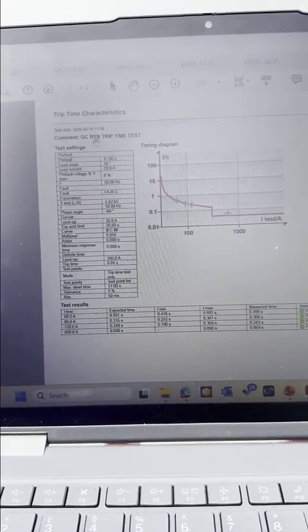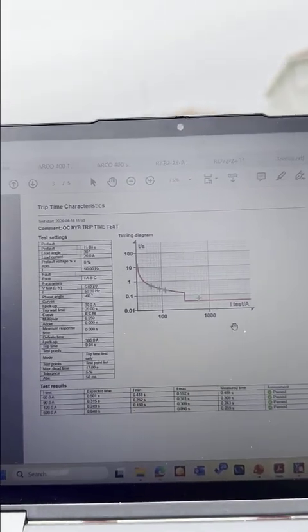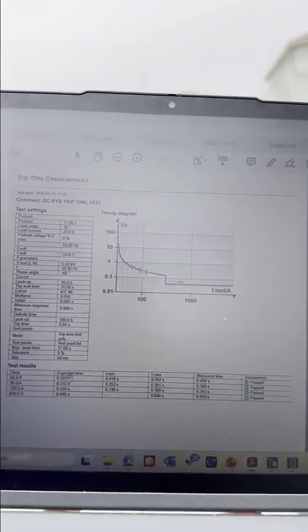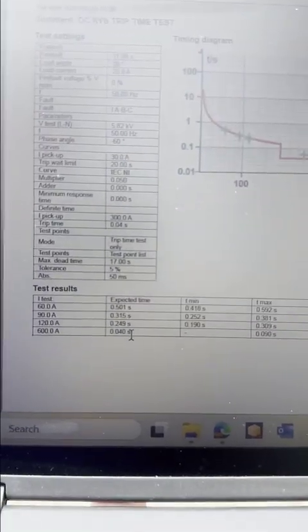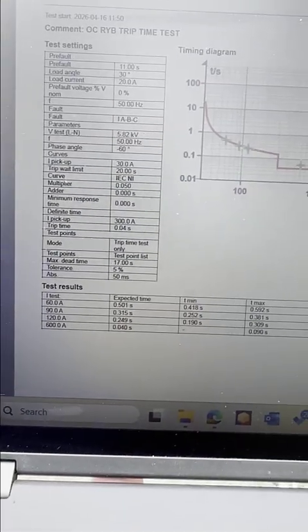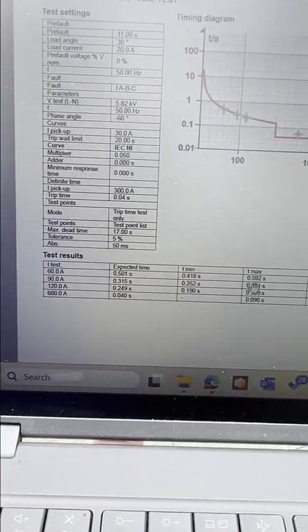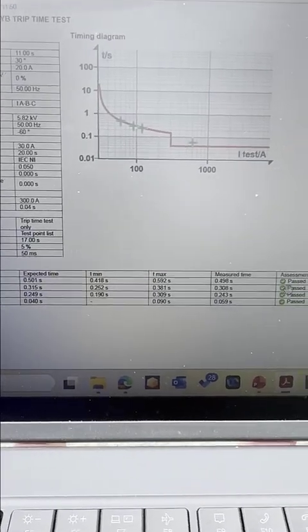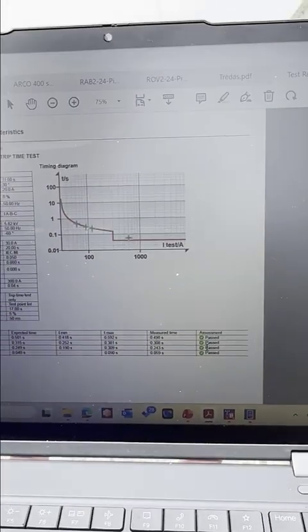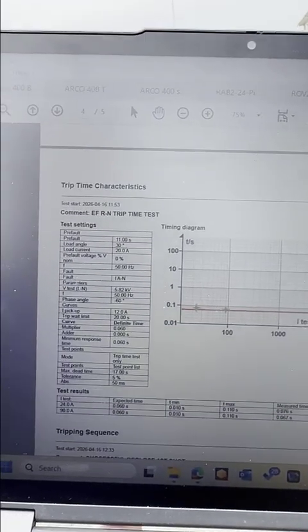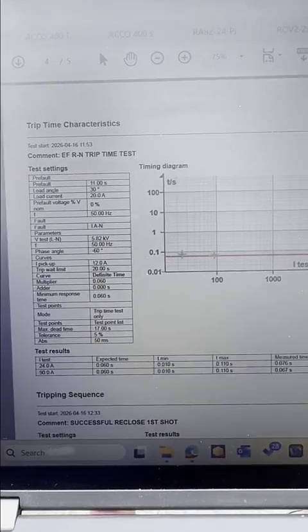Then you can see here the trip time characteristic for the overcurrent RYB trip time test with the 3 shots we injected, and here is the expected trip time based on the curve equation, and here is the measured trip time, and here is the tolerance band from the minimum to the maximum, and whether it's assessed pass or fail. This is automatic assessment. Also you can see the same for the earth fault. We have only one stage, different time. You can see it from here.